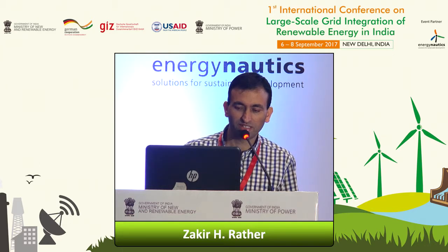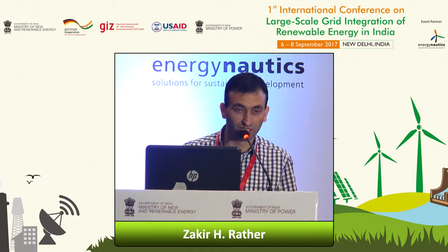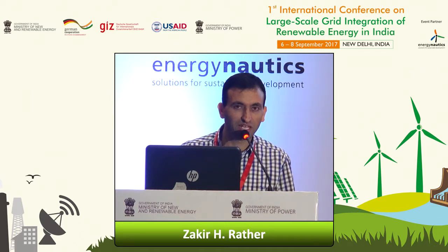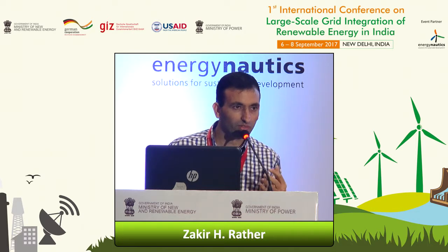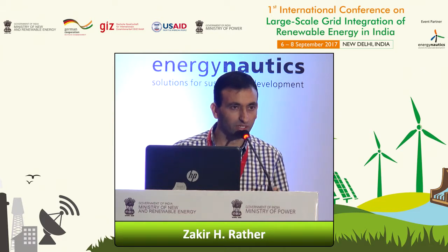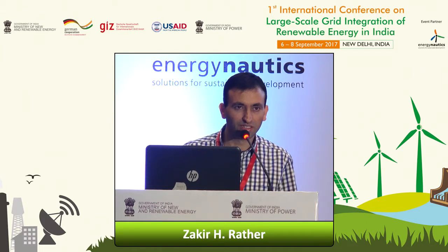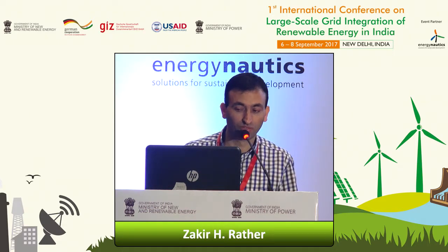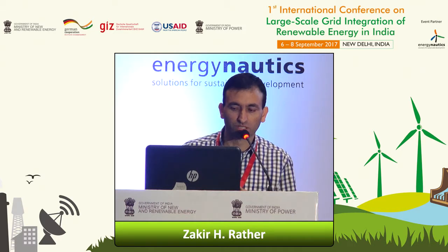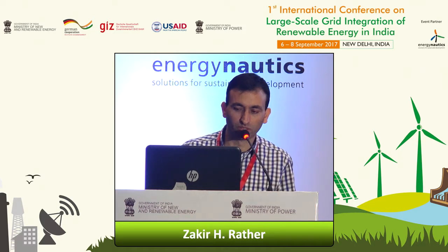But if you see, there is a delay in the recovery of the frequency in case of this inertial response only. The reason, as I mentioned in the previous presentation, was that following the event, the wind turbines try to catch up with the speed. As a result, there is a net decrease in the power production of the wind turbines, and there is a delay in the recovery of the frequency. That is also very important. The recovery of the frequency, or in other words, the quality of the frequency, is also important.